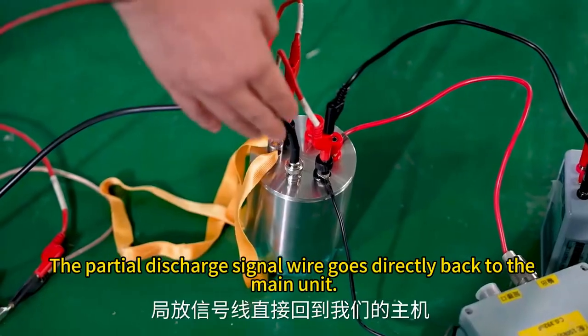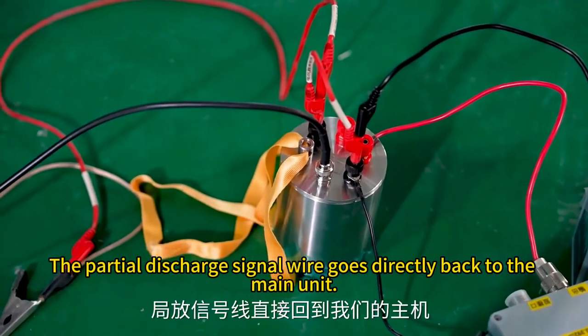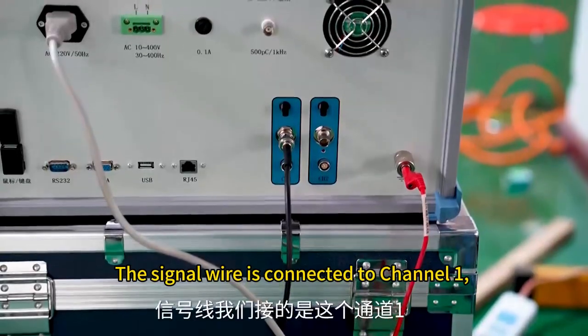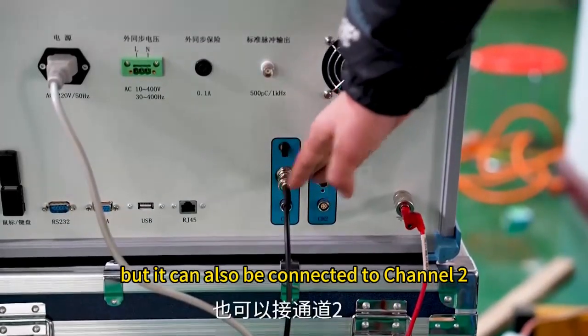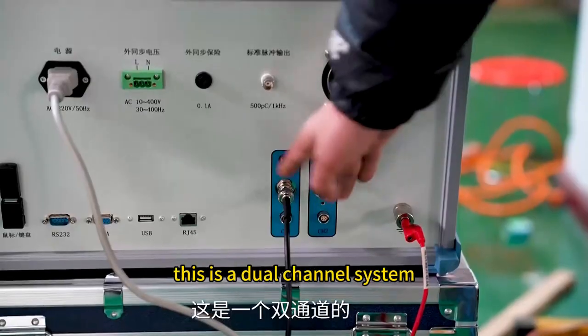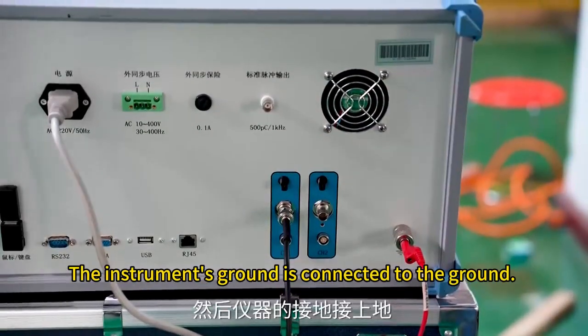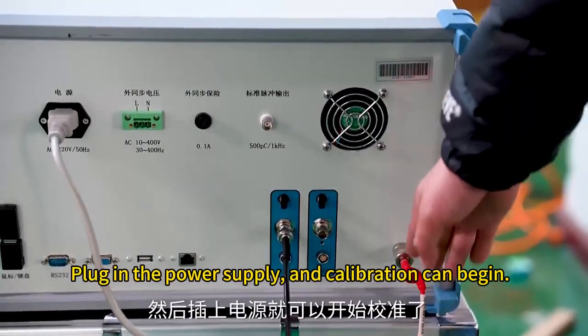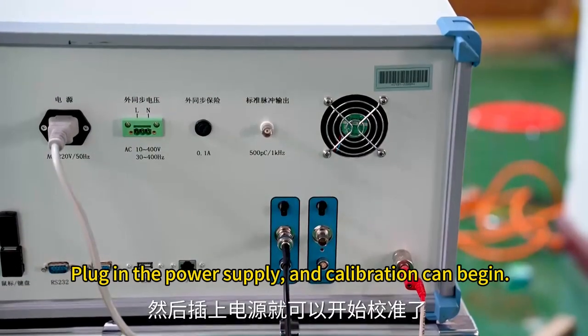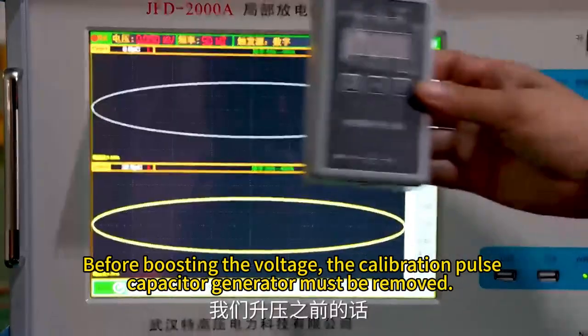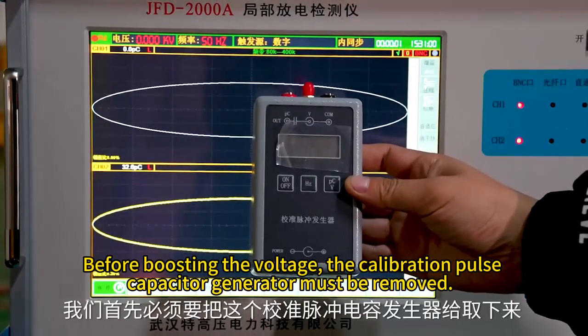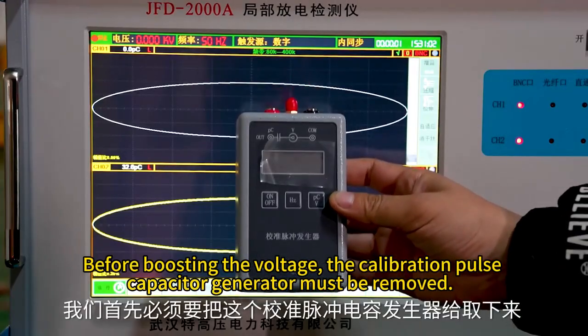The partial discharge signal wire goes directly back to the main unit. The signal wire is connected to channel 1, but it can also be connected to channel 2. This is a dual-channel system. The instrument's ground is connected to the ground. Plug in the power supply, and calibration can begin. Before boosting the voltage, the calibration pulse generator must be removed.